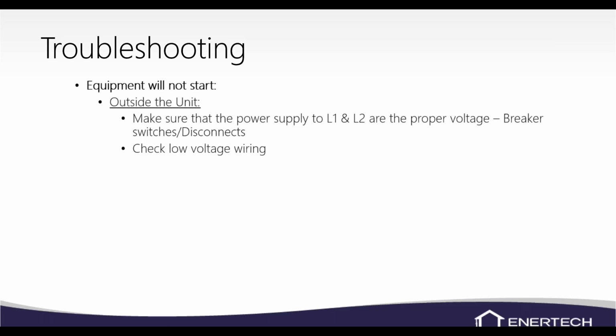Check your low voltage wiring. There is a fuse on the ECM board for the low voltage side of it. And again, if you do suspect the low voltage, just remove it from the equation and jumper the unit out and see what happens. If you look at the lockout board, there's a status light on the lockout board, a green status light on the very bottom of the board. If you've got low voltage to the unit, that should be flashing all the time. The only time that will not flash is if you pull the test jumper or flip the test into the off position, and that light will go away.